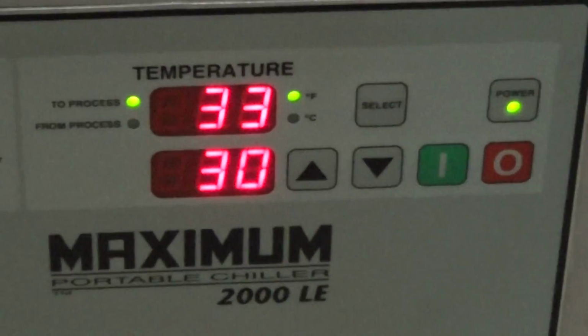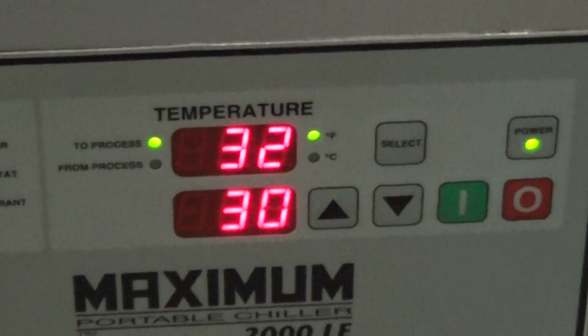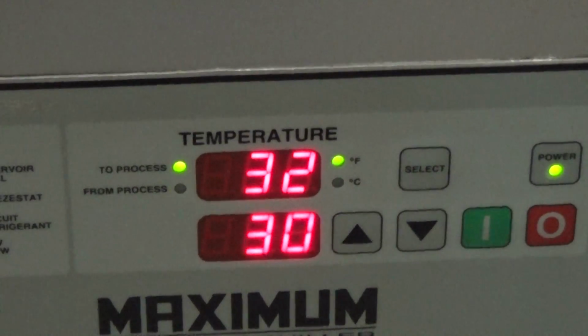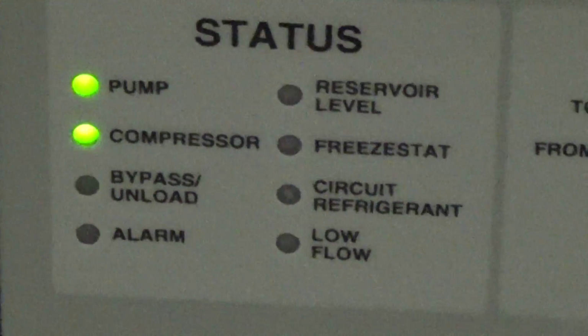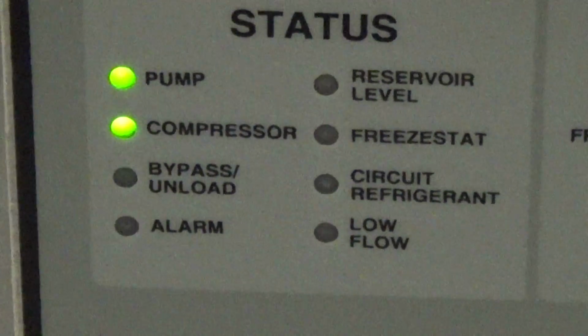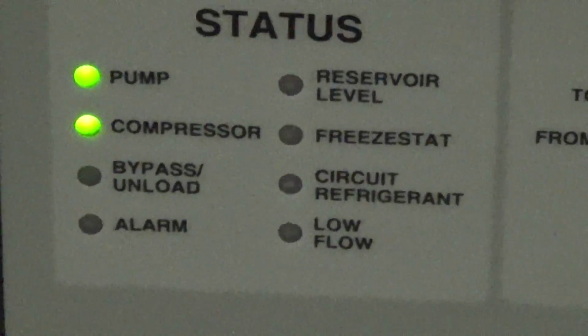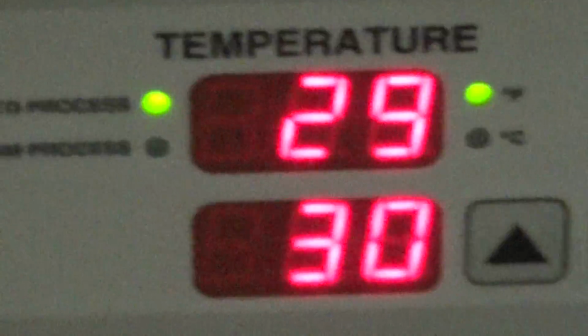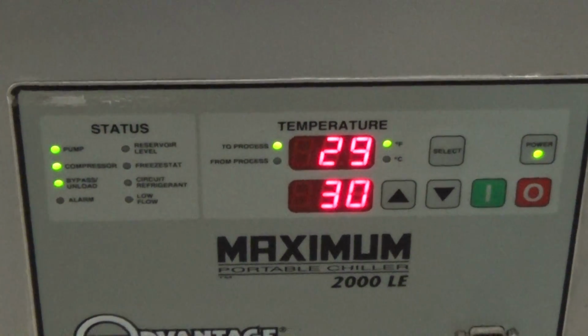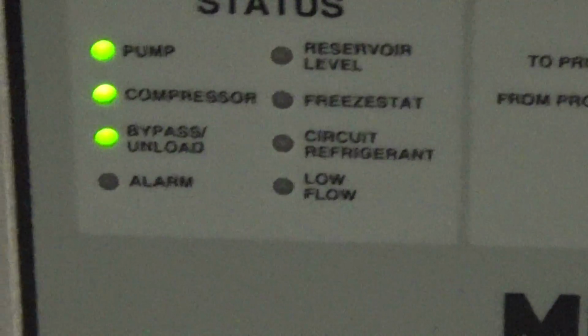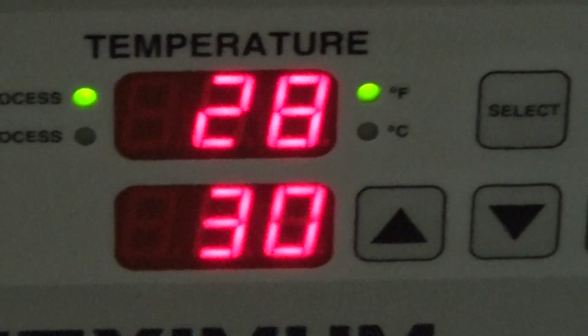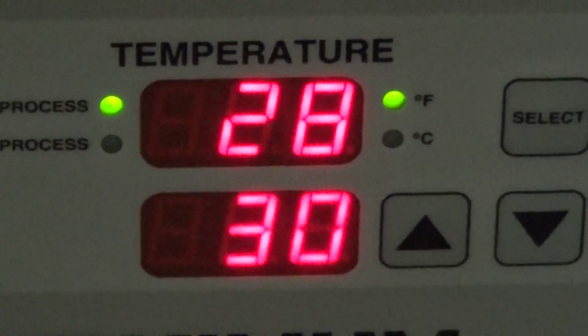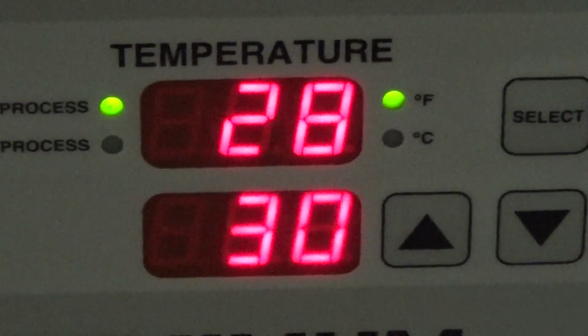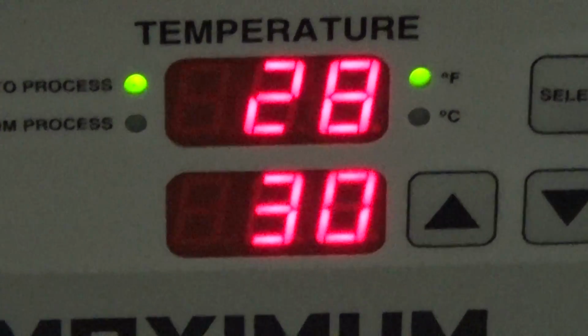When you get a few degrees below the set point, or maybe prior to that, you should hear a hissing, and that's the hot gas bypass engaging. On the screen, it's called bypass unload. Actually, every control is a little bit different. This one gets about a degree below set point before that turns on, and you can hear that hissing. That's the solenoid valve opening up for the hot gas bypass. And this will probably go to 27 or 26 degrees before it turns off. And then it'll go a degree or more above the 30 degree set point before it turns back on.